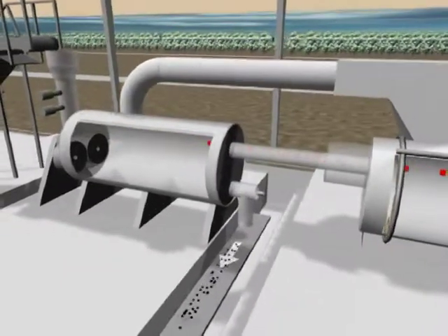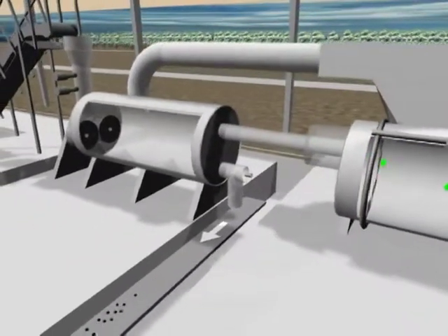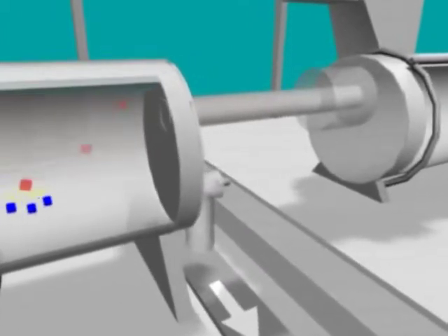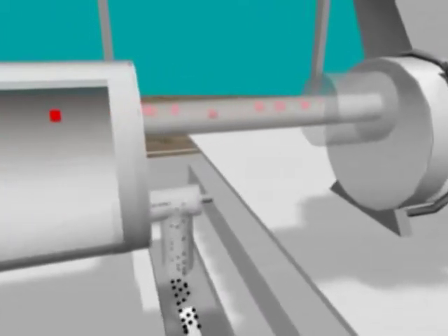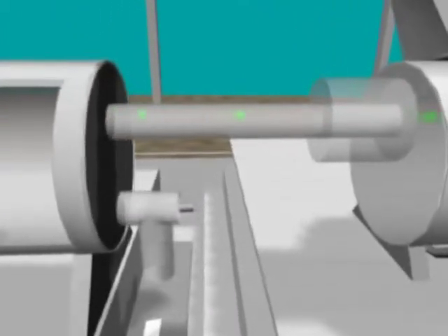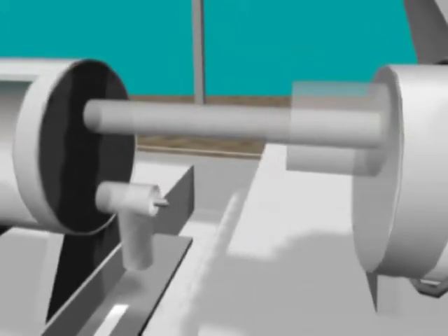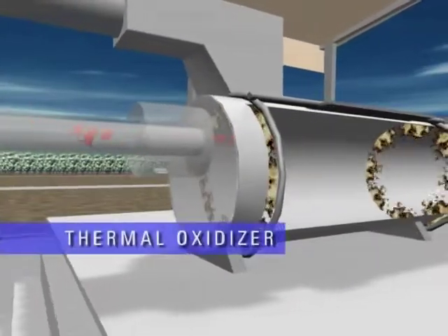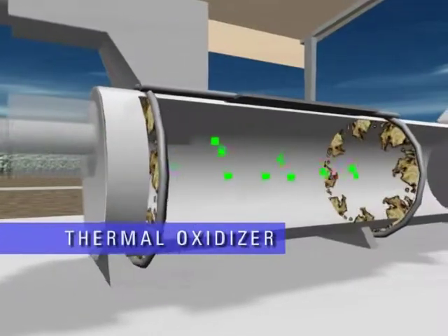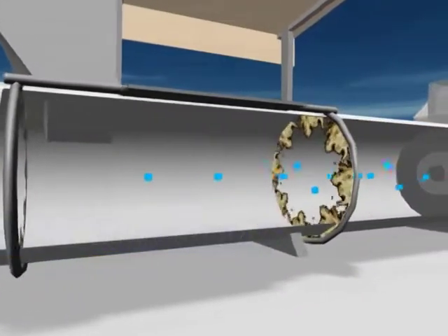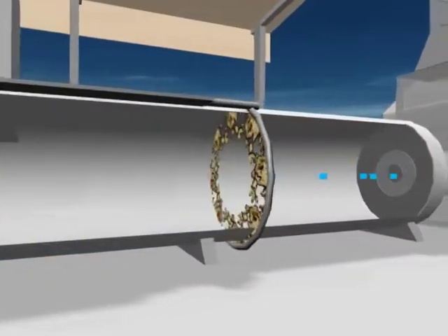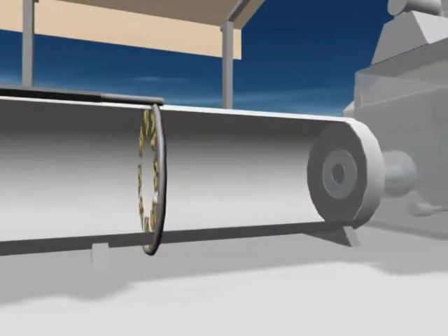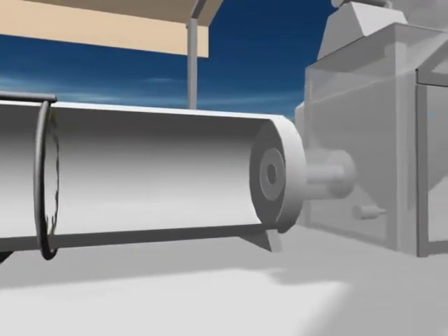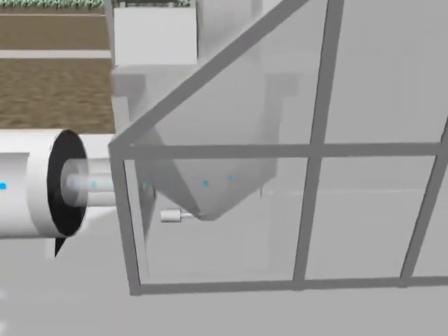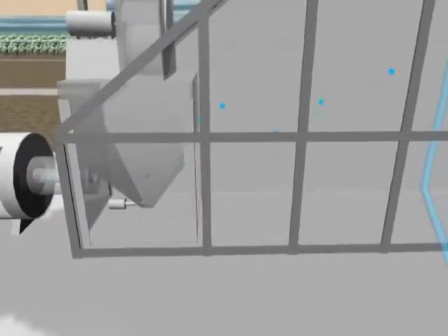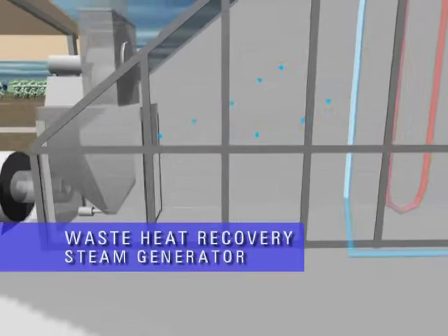These products are separated via gravity, with the solid carbon char dropping out of the bottom of the pyrolytic chamber and the gaseous product being vented to the entry of the thermal oxidizer. In the thermal oxidizer, the off gases from the pyrolytic chamber are subjected to a high temperature oxidation process. As the now oxidized gases leave the thermal oxidizer, the high temperature, high energy potential of the exiting flue gas is heat exchanged to a waste heat recovery steam generator.